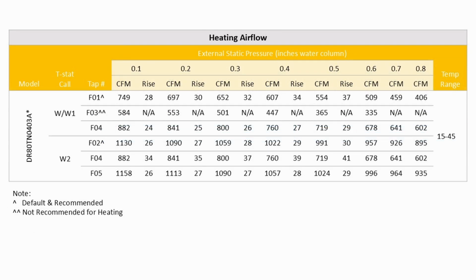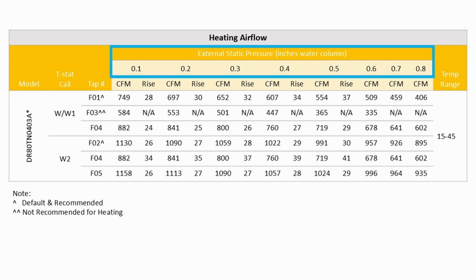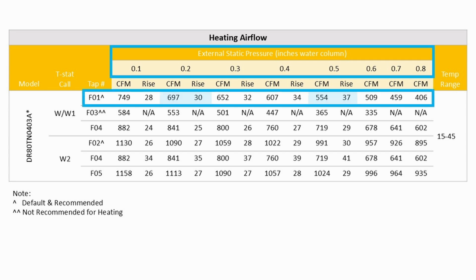In heating mode, for a call for W or W1, at the default speed at 0.2 inches of static pressure, the CFM is 697 and the temperature rise is 30 degrees Fahrenheit. At 0.5 inches of static pressure, the CFM is reduced to 554, the temperature rise is increased to 37 degrees Fahrenheit.